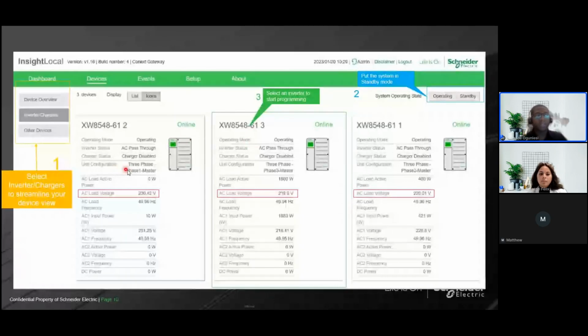Typically, by default, each of them is going to be set to single phase master. You have to change this to either three phase line one master, like you see here, three phase line two master, or three phase line three master. Or if it's a single phase installation, this could be your single phase line one master, or single phase line slave, single phase line slave again.